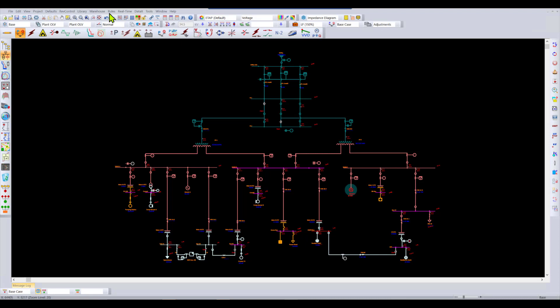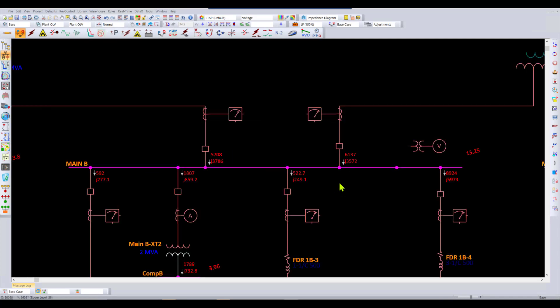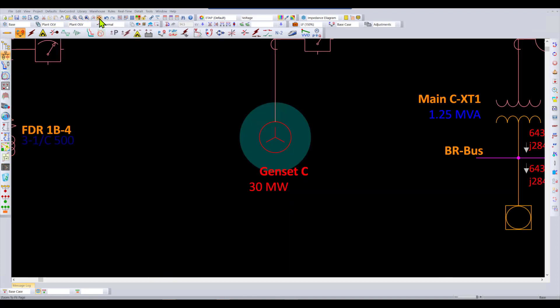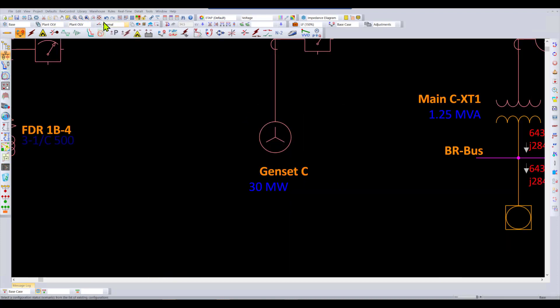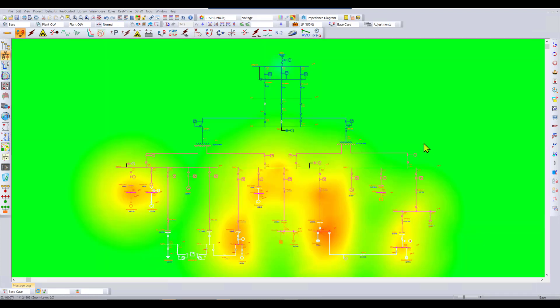Here we can see that in certain parts of the system with the magenta color, there are certain buses that are under voltage in the network, and we want to have a bit more of a flatter voltage profile in the electrical circuit. We can quickly see what's going on by turning our color contouring on.